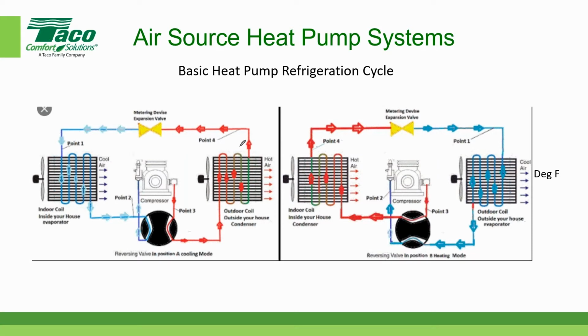This guy on the left, I just showed that in the previous picture as a refrigerant to water heat exchanger, but this one is a refrigerant to air heat exchanger. But what I'm really interested in, which is why I'm showing this diagram, is the reversing valve. So it leaves the compressor as a high temperature, high pressure gas. It goes through the reversing valve and then goes into the condenser.